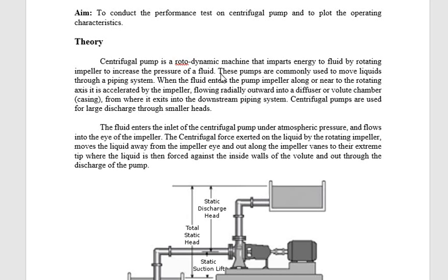These pumps are commonly used to move liquids through a piping system. When the fluid enters the pump impeller along and near to the rotating axis, it is accelerated by the impeller and flows radially outward into a diffuser or volute chamber, from where it exits into the downstream piping system. Centrifugal pumps are used for large discharge through smaller heads.